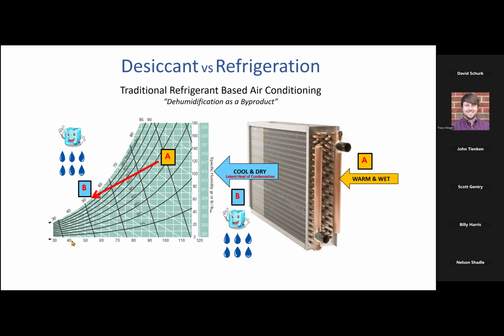I have to continue to deeply cool it in order to drop its temperature, drop the surface temperature of the coil, drop the temperature of the leaving air, and condense more moisture out of it. It's the only way I can accomplish deeper dehumidification with a system like this. Colder surfaces, colder fluids, colder leaving airs, etc.